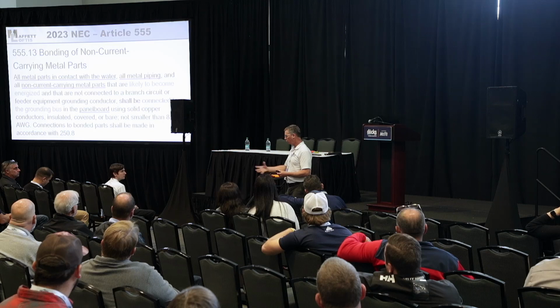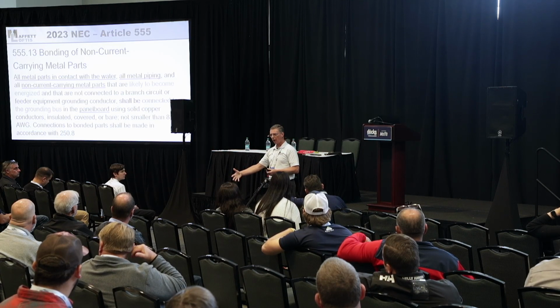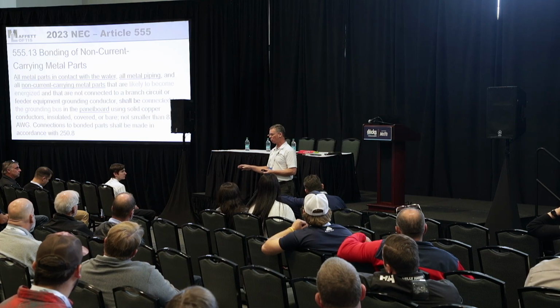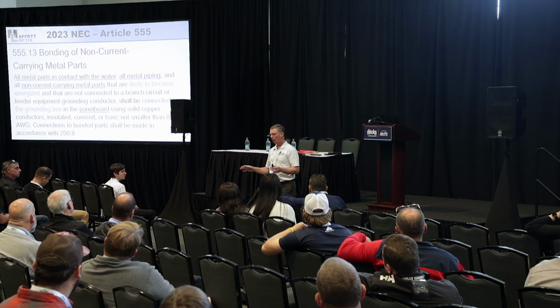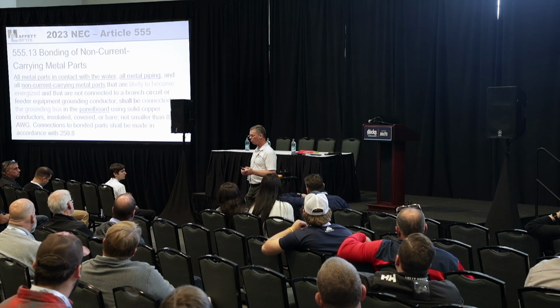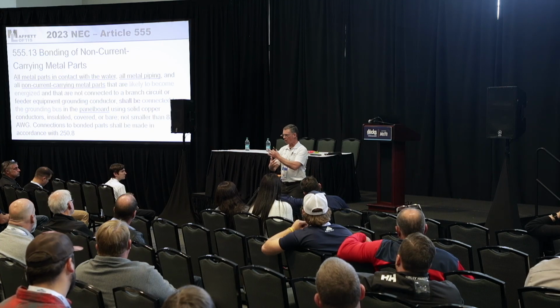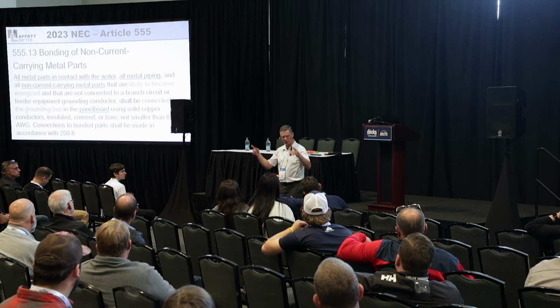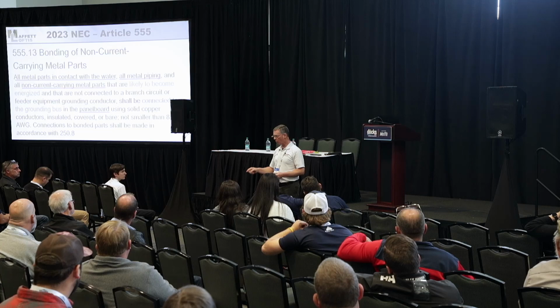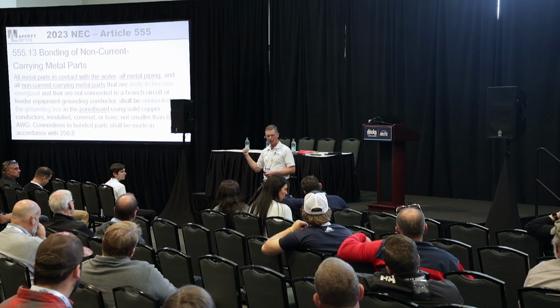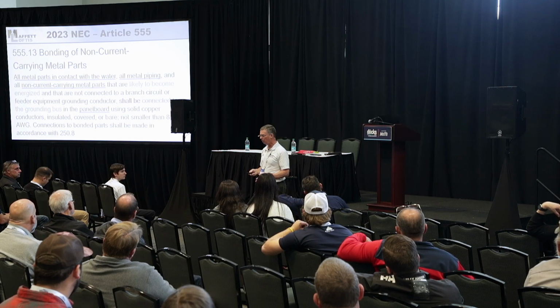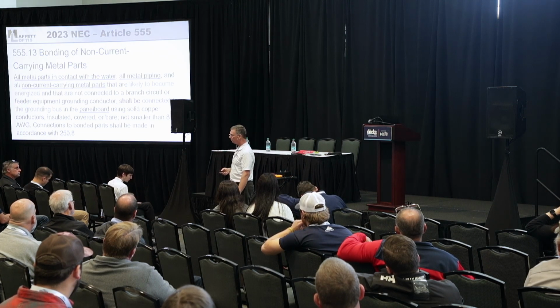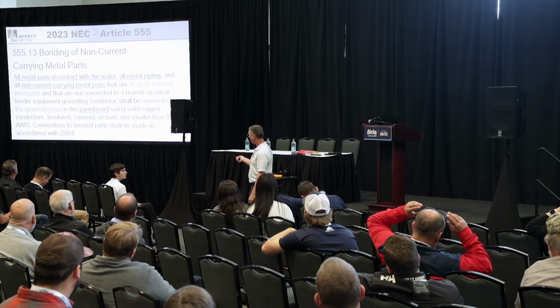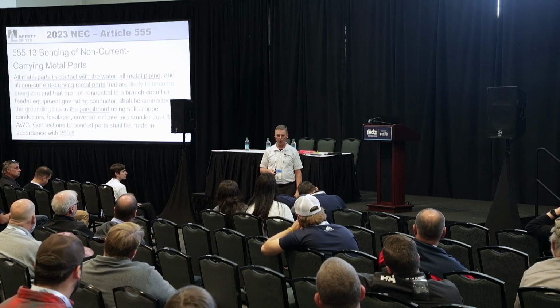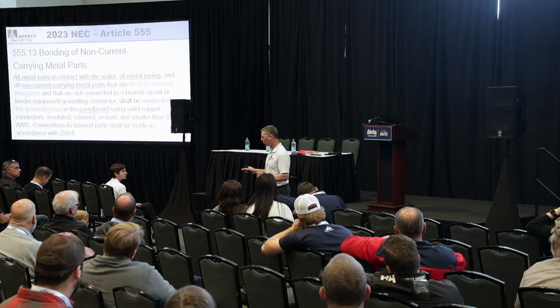There are a lot of dock manufacturers that use little metal gusset plates in the corners sometimes, and they're in contact with the water. They're not likely to be energized. There's no conduit, no wiring anywhere close. We even have an inspector down in South Florida on the West Coast, on timber frame docks, with the cross bracings underneath. What are they bolted to the pilings with? Through bolts, which are metal. He's saying that all those metal bolts in contact with water have to be bonded back to the panel. Every winch stand, every piece of metal in contact with the water, they're making them bond it down in Florida, because they're reading that likely to be energized applies only to that third piece of metal. That was not the intent of the code-making panel when this was written.